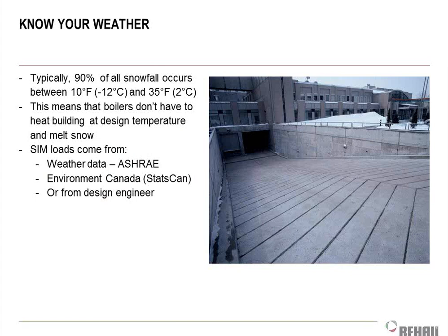Now, in some applications, the snow melting becomes a more dominant load than the space heating even, and we got to do it a little bit differently. But if you're just talking about your house and you want to go heat some snow on your sidewalk, that would be pretty easy. If you got a 2,000-foot driveway, a little bit different discussion. We're going to have to size your boiler differently.